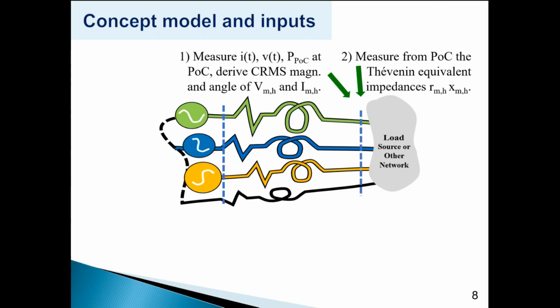Complex because it's magnitude and angle, RMS because we're looking at the RMS values of sinusoids and not at the peak value. And we do that for each wire, M, and each harmonic, H. So what we're looking at is taking that distorted signal at the POC, using a Fourier transform to identify the frequency components, and measuring the impedance from the POC looking into the delivery system.